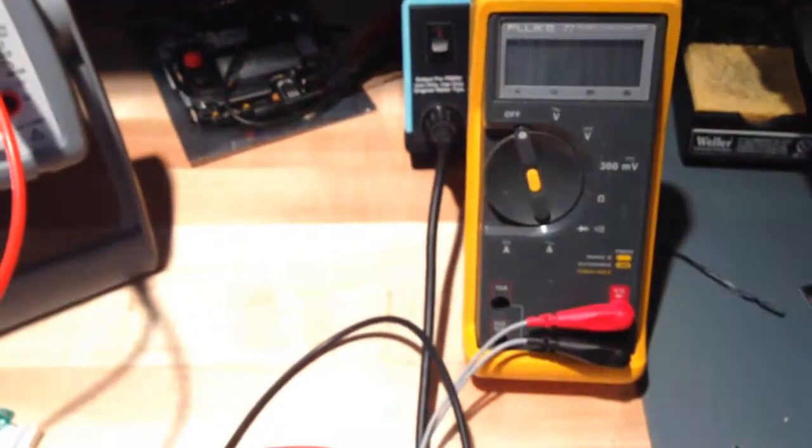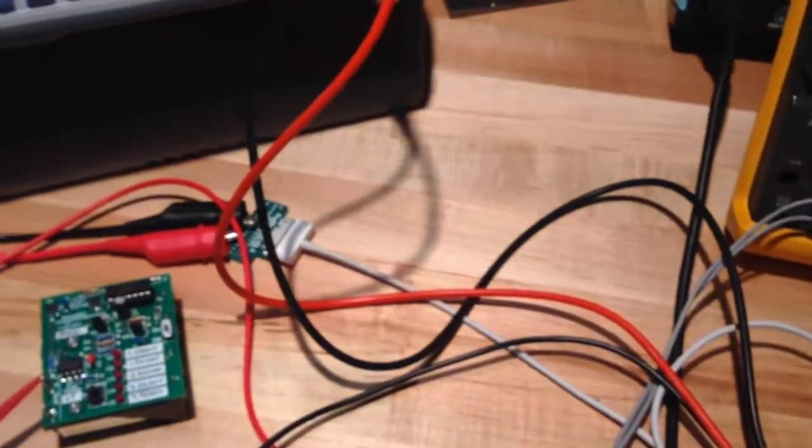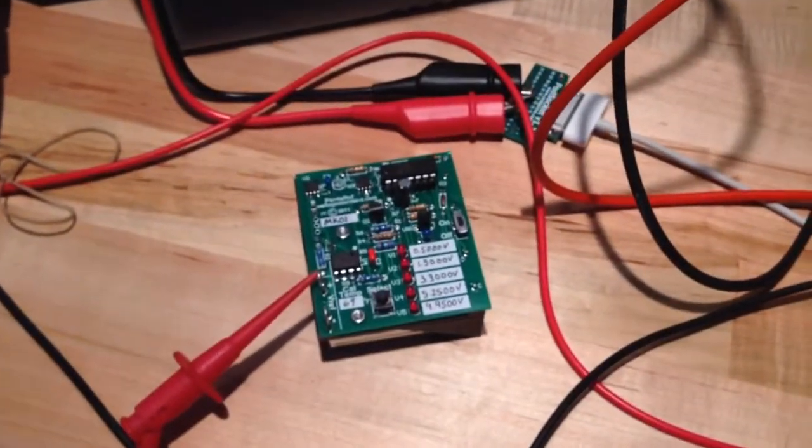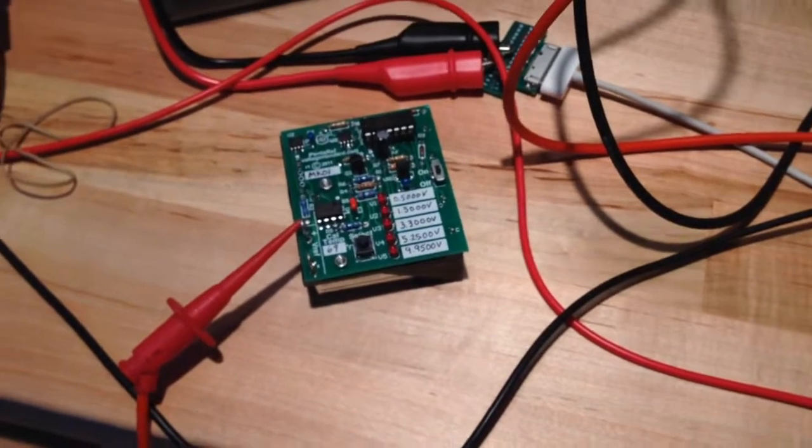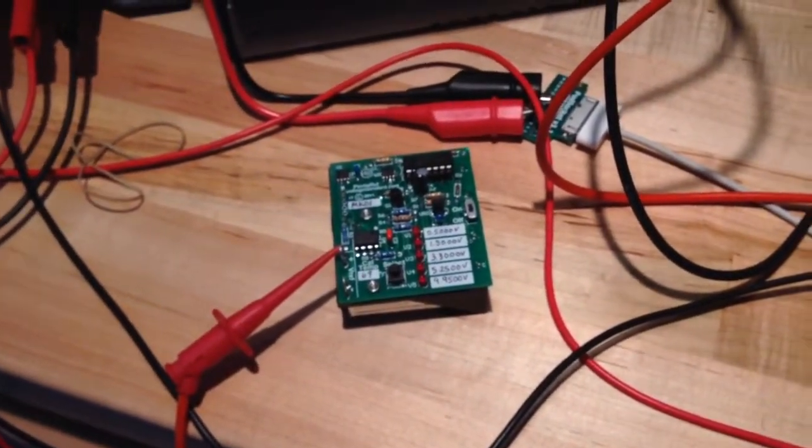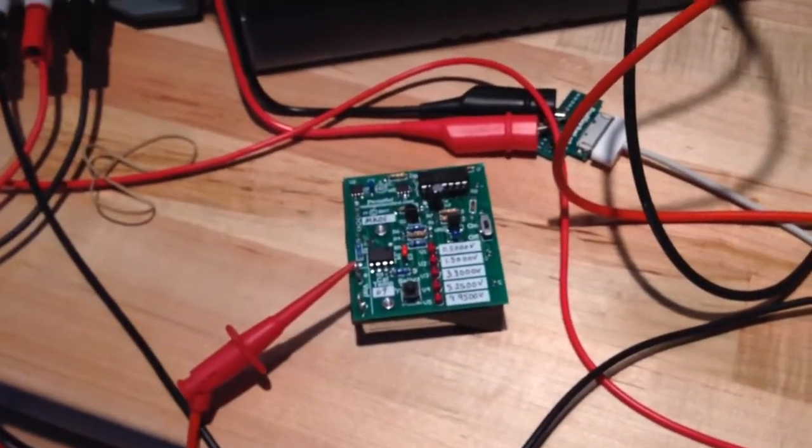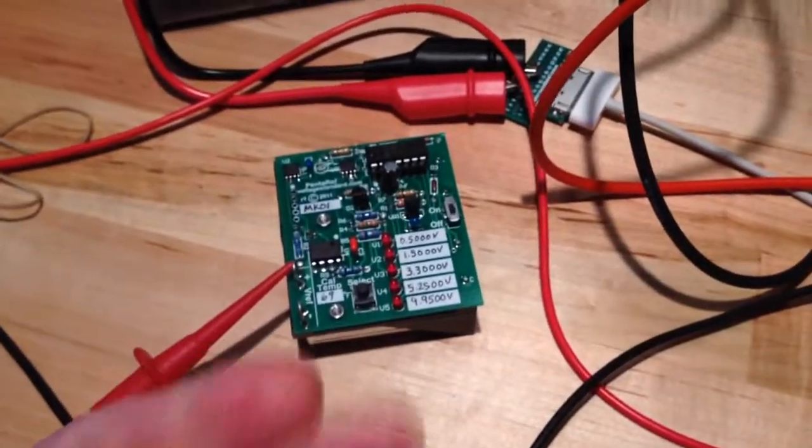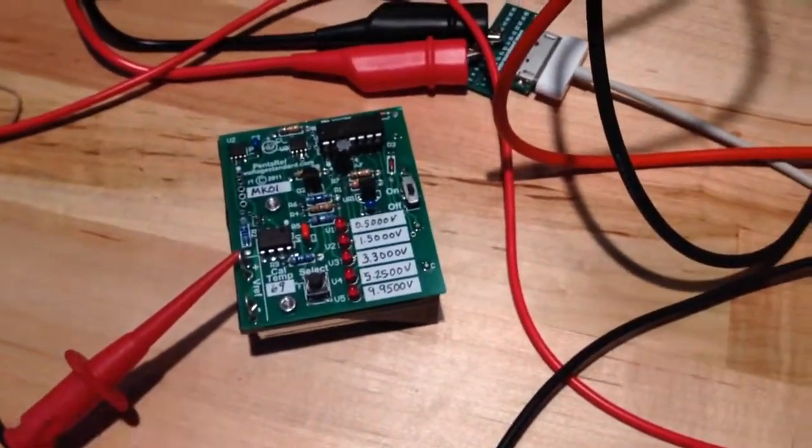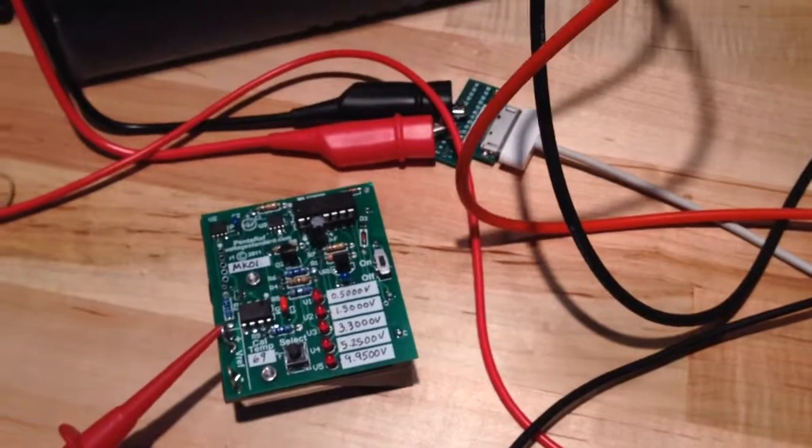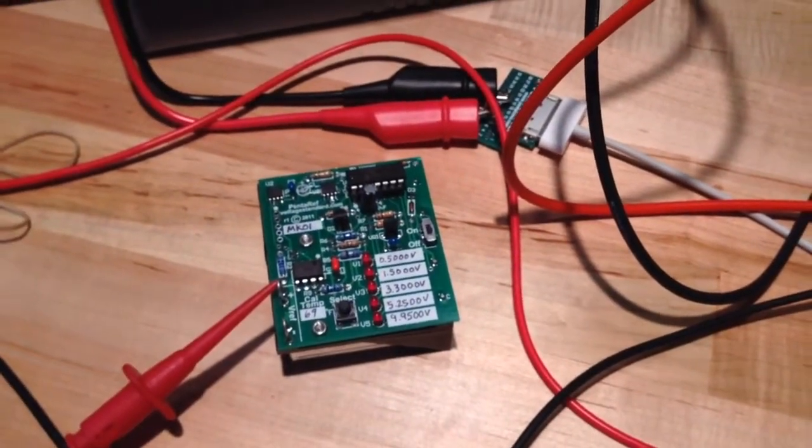It could be used with any other kind of digital multimeter as well like this Fluke 77. Obviously not as high resolution as this Agilent but it does the job. So if you're looking to have a reference around the lab that doesn't have to be too precise, I mean these things are pretty darn spot on. But again, it gives you a nice reference to have in your lab.